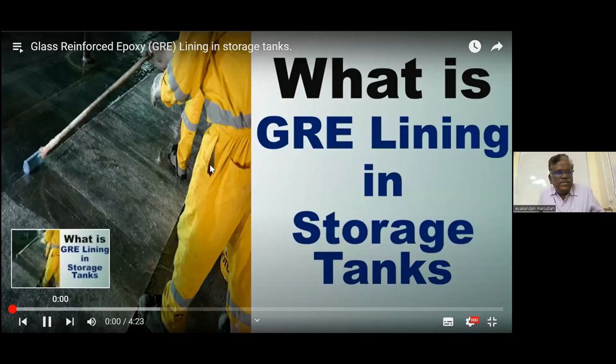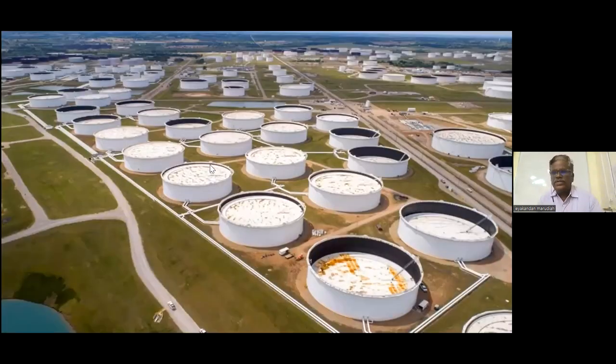Chemicals can be severely corrosive to above ground metal storage tanks, resulting in possible leaks. The average corrosion rate of some carbon steel storage tanks in certain services at ambient temperatures is more than 1 mil per year, with leaks developing in as few as 5 years. These leaks result in costs for both tank repair and possible environmental penalties.